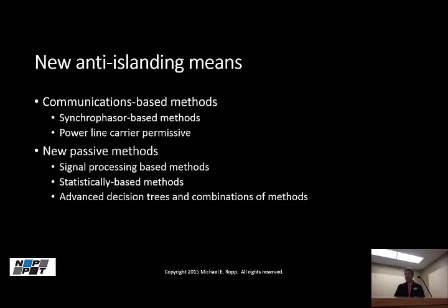Speed has been the problem. It usually detects within 2 seconds, but not always. It's a statistical method, so the run-on times then vary statistically. We're working on that to try to improve it, so that's kind of where that work is at this point. But the beauty is there are some communications channels, some broadcast comm channel possibilities that might make the synchrophasor-based approach one in which the communications costs can be significantly reduced. So again, a lot of promise in both of these methods. It's not clear at this point which one is going to be the market winner, if you will. And there are people actively working on both.